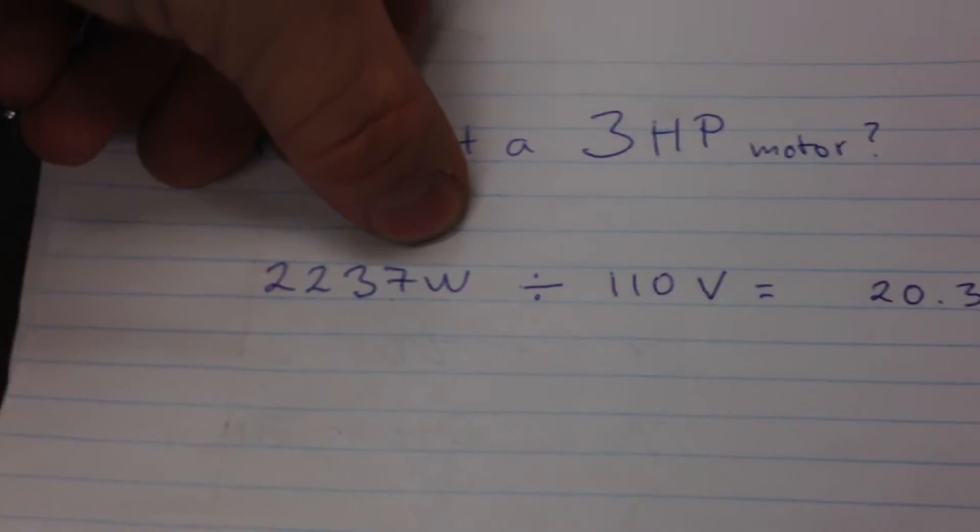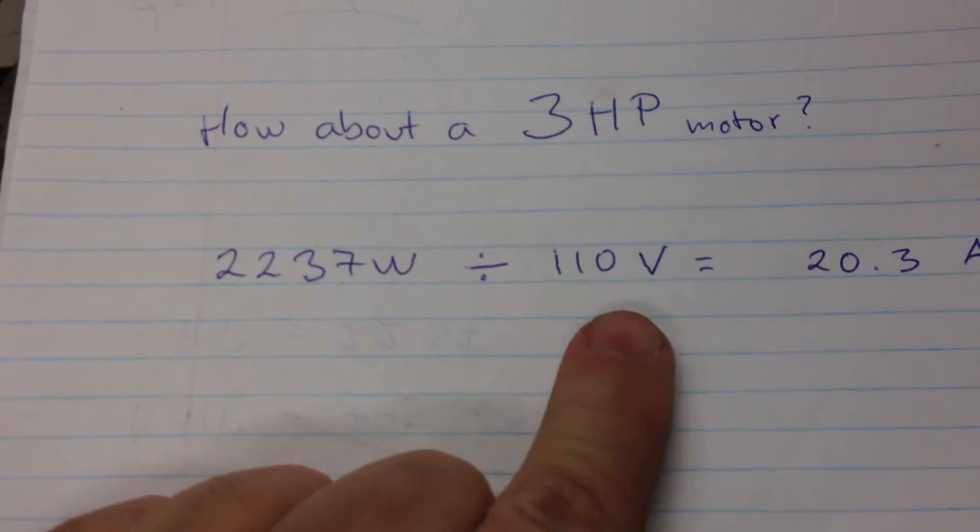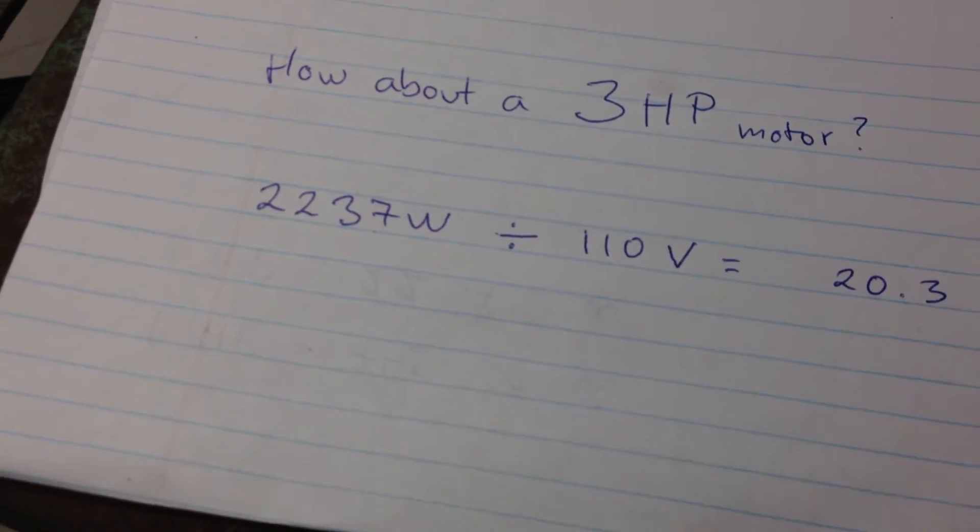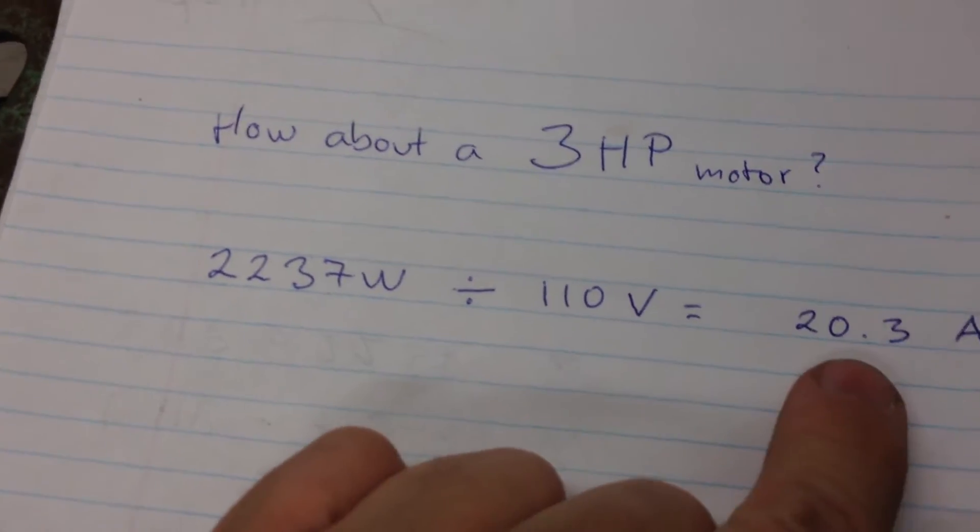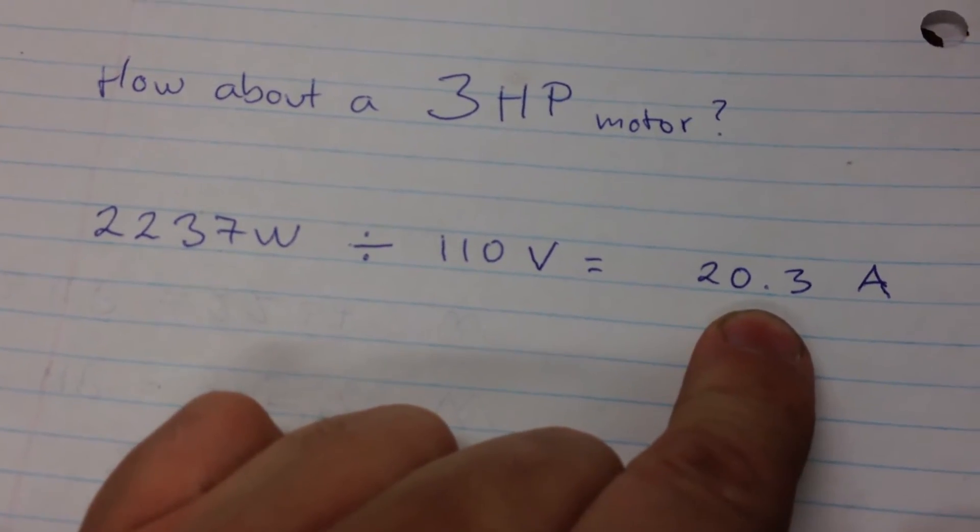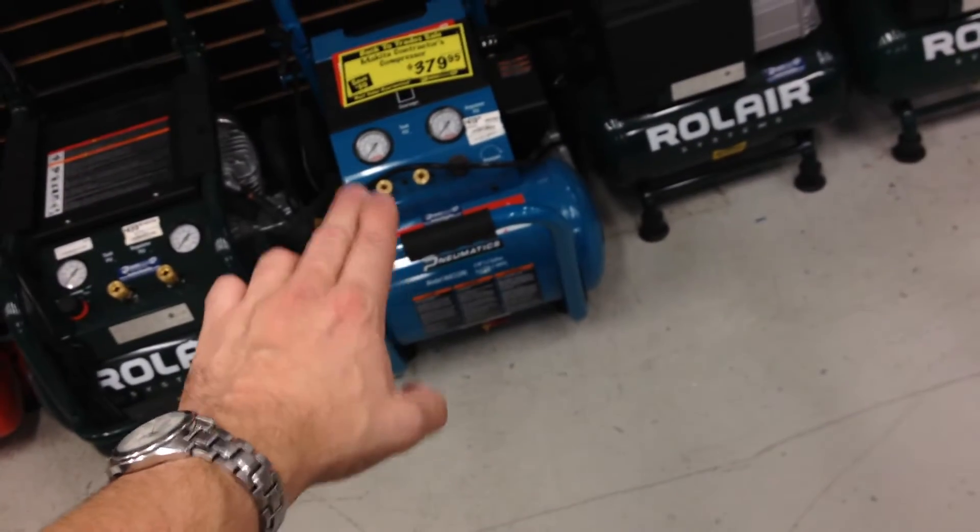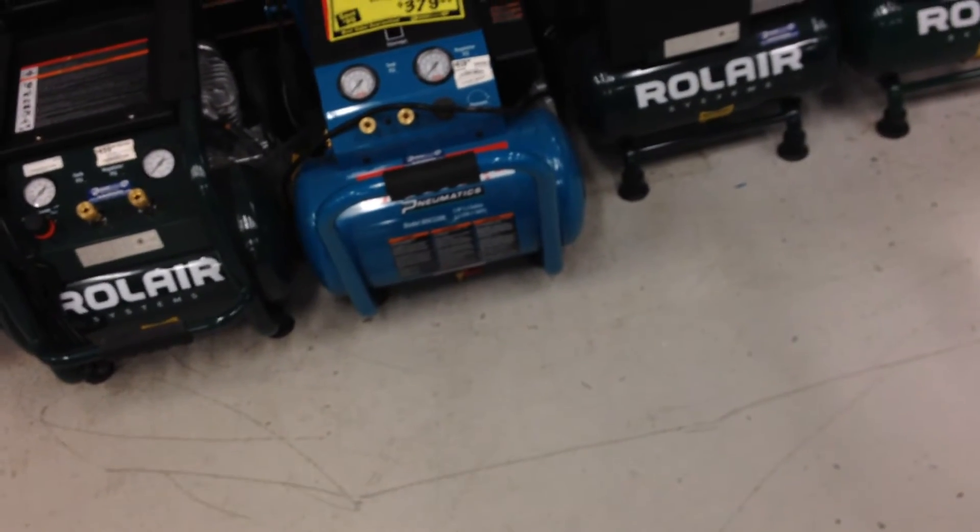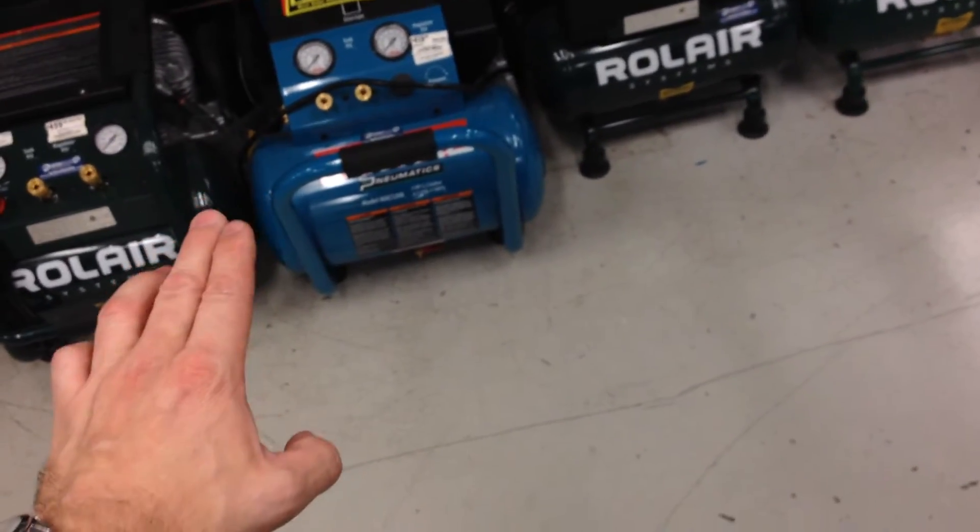That's going to give you 20.3 amps. 20.3 amps is not 15 amps. There's no way you can plug in that product if it really is running on a three horsepower motor to a 15 amp circuit and not trip the breaker.